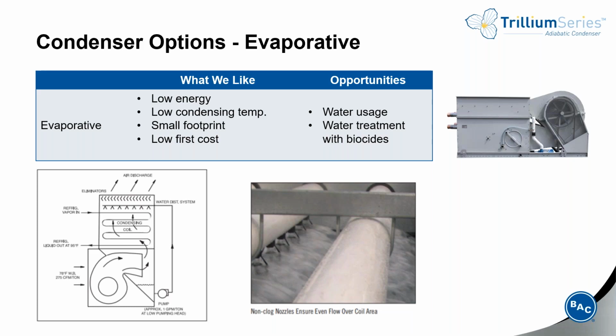There are some costs associated with the benefits that come with evaporative cooling, and these include high water use and the need for chemical treatment. Evaporative cooling products feature large sump basins and spray water distribution that may produce aerosols. And for this reason, chemical water treatment is needed for biological growth control and for scale prevention on the heat exchanger surface.